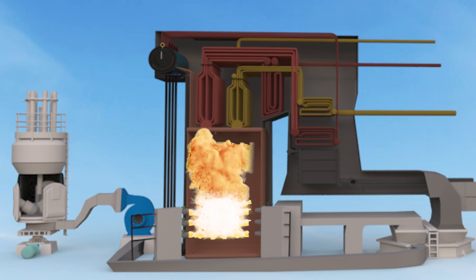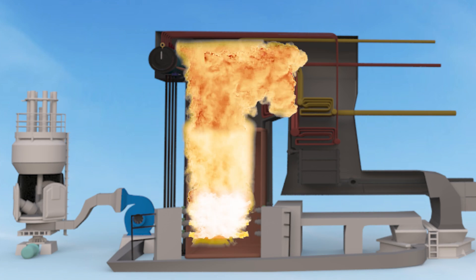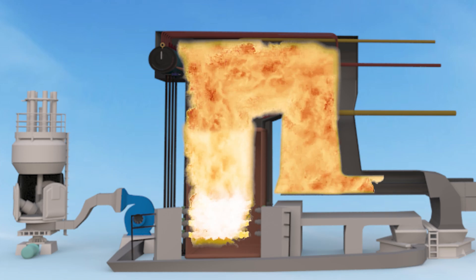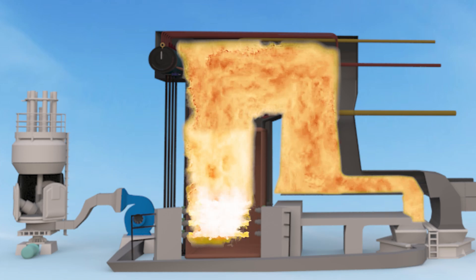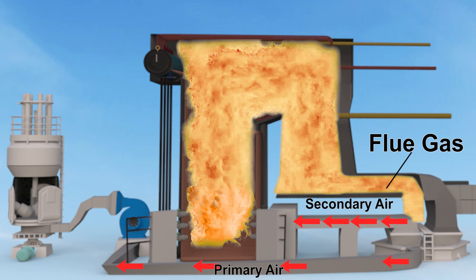The air preheater recovers heat of flue gas and heats up ambient air which passes through it. This heated air gets divided into two streams. One stream, called secondary air, is sent to the furnace by the FD fan — which we have already covered in our previous video. The second stream of preheated air goes to the pulverizer or mill.